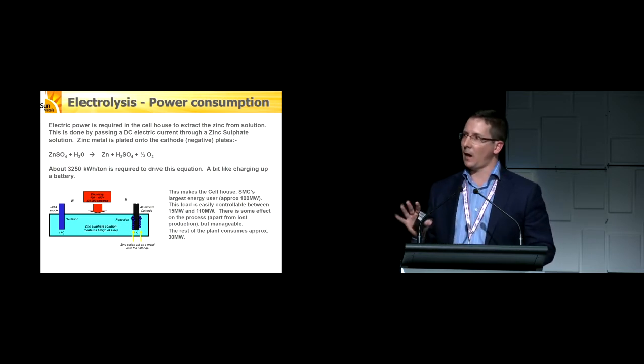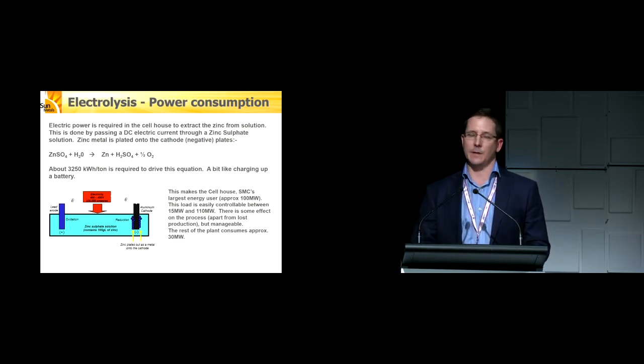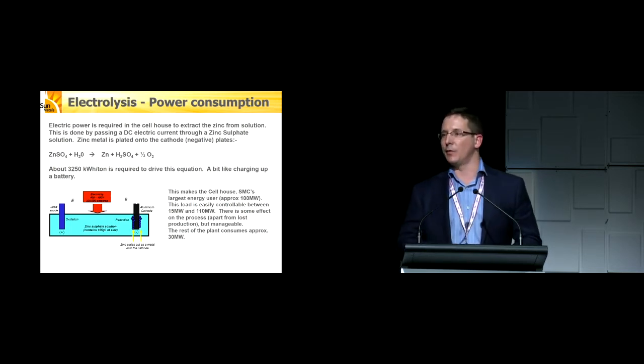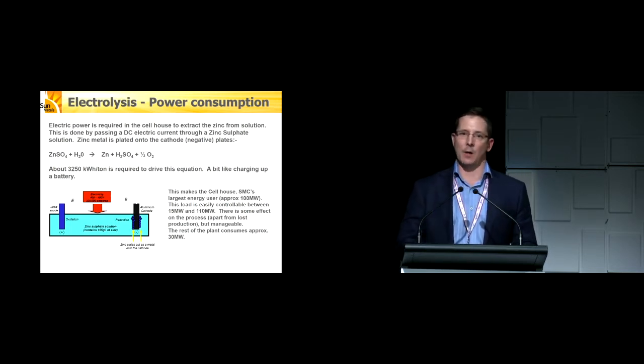And the cell house is very easily controllable. The production rate is directly proportional to the applied current, to the power consumption, and we can control that production rate. We can go very quickly from a minimum holding current of 15 megawatts in that plant up to a maximum production rate of 110 megawatts. And at 110 megawatts, we're producing about 40 tonnes per hour of zinc metal.